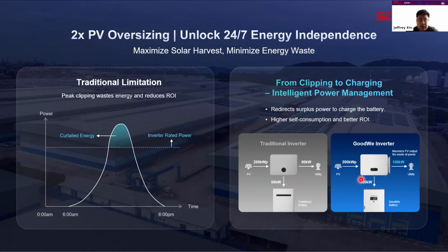But for our inverters, you don't need to worry about power waste, because we can divide it into two parts of output and charging independently. For example, if you use a 100 kilowatt inverter but connect 200 kilowatts of panels, 100 kilowatts can be used for consumption and another 100 kilowatts for battery charging.